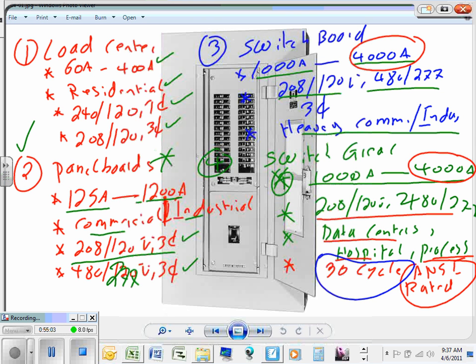Switchboards, by the way, are 3 cycles. All this equipment here is 3 cycle equipment. Switchboards are 3 cycles. That's why you pay 25 to 30% more on a switchgear, even though they look alike and do the same function. You pay 25 to 30% more money-wise if you specify switchgear. Any questions, guys? So that's basically in terms of panels. Really, as an engineer and as a designer, that's what you need to be aware of when it comes to switchgears and switchboards.